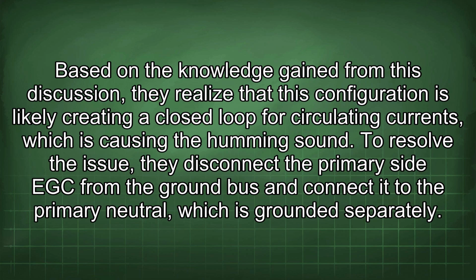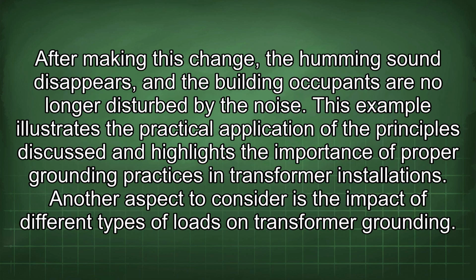To resolve the issue, they disconnect the primary side EGC from the ground bus and connect it to the primary neutral, which is grounded separately. After making this change, the humming sound disappears, and the building occupants are no longer disturbed by the noise. This example illustrates the practical application of the principles discussed and highlights the importance of proper grounding practices in transformer installations.